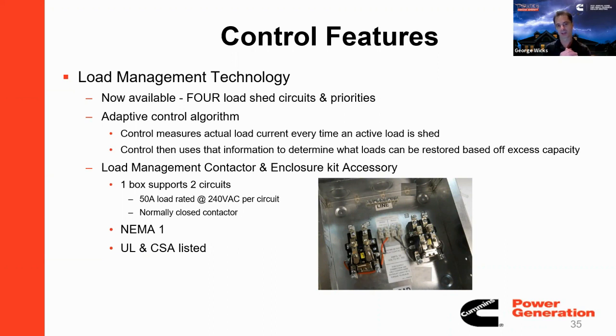So he talked about how it's adaptive, what it learns over time. Load 1 is air conditioner 1. If it needs 6 kilowatts to start that, it's going to see its percent load. If it's running at 80%, it's not going to bring number 1 on. If it's running at 20%, it's going to go ahead and start number 1. And from the same history, it learned about 2, 3, and 4, and how much it stepped up each time one of those turned on. So it's going to try to bring them on in sequence, up until like 90% load, and it'll keep adding loads up to 90% load.